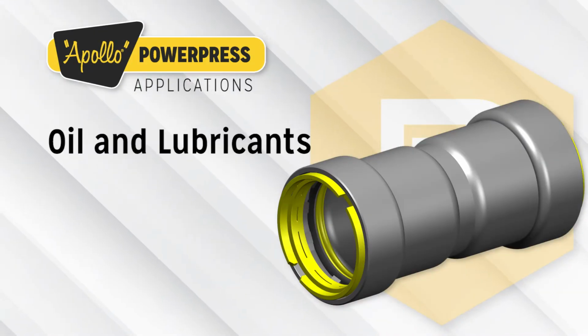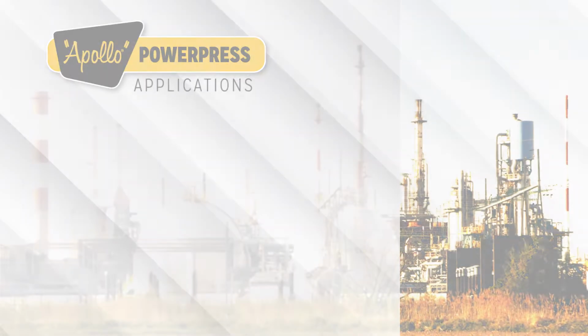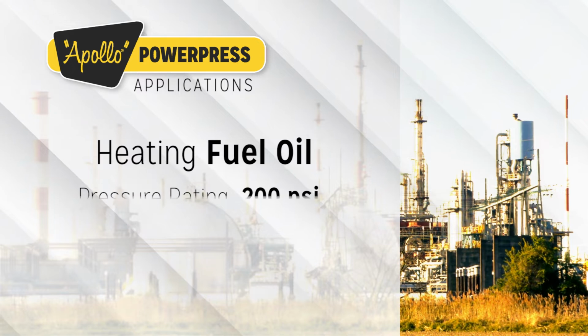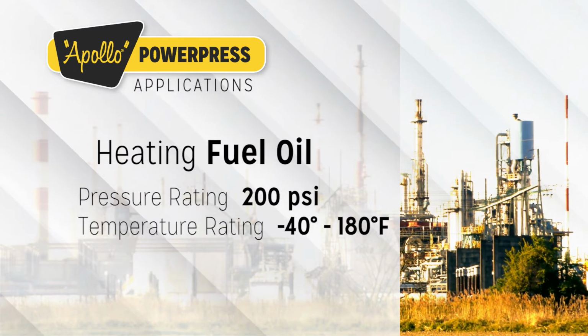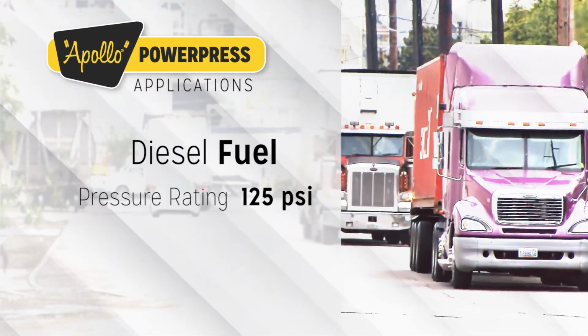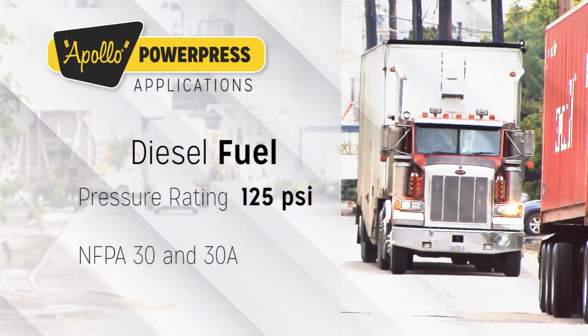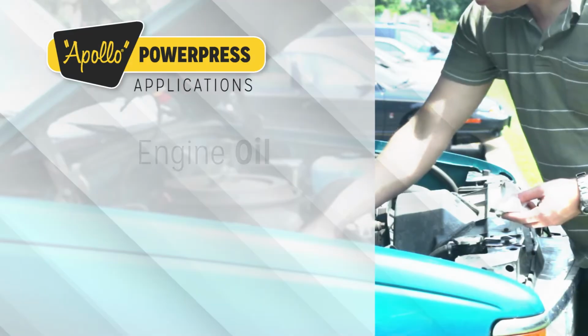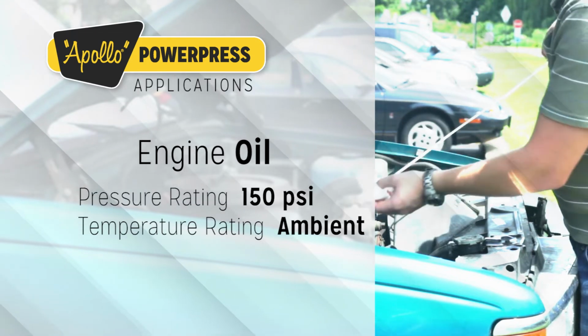Oil and lubricants are approved with HNBR sealing elements and include the following: heating fuel oil, pressure rating 200 psi and temperature range of -40 degrees to 180 degrees Fahrenheit. Diesel fuel is rated at 125 psi and compliant with NFPA 30 and 30A. Engine oil, 150 psi with an ambient temperature rating.